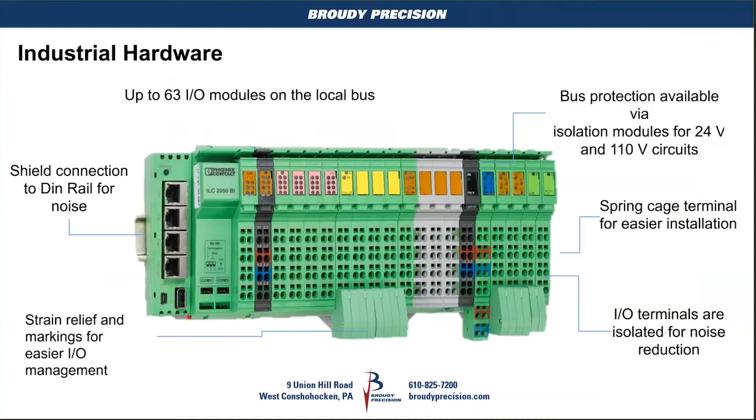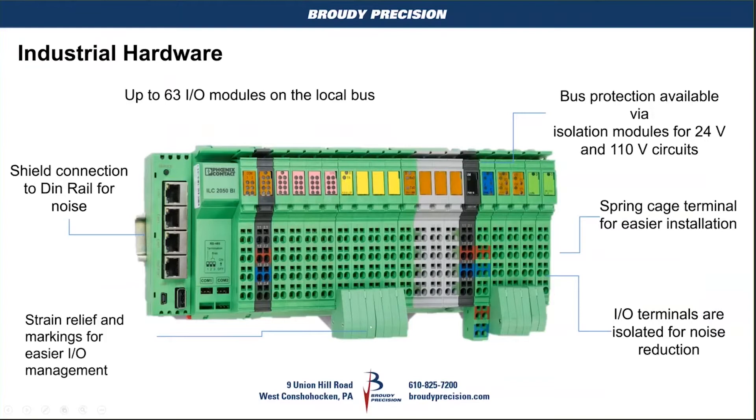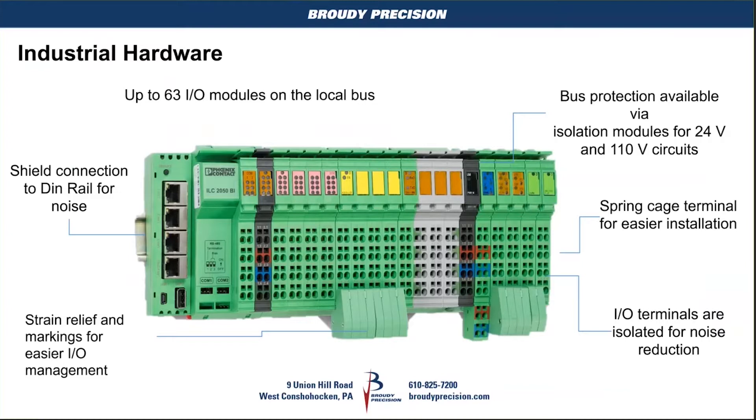Here's a representation of the ILC 2050 with IO modules. There's a power module, that black module there is part of the Jace and everything to the right of that is IO. So it could be a plant controller. There's strain relief, they've got spots where you can put in tags and markers for tagging each of these cards. The size of a regular Jace is about six modules, so this module here to the left is basically the size of an 8000.